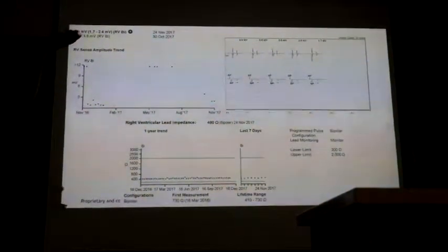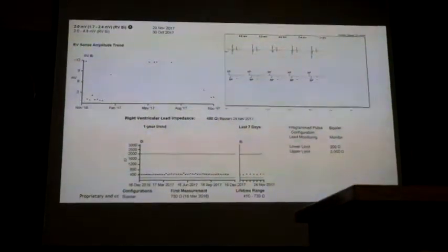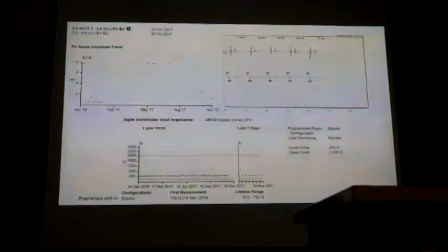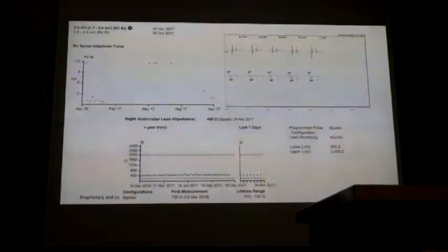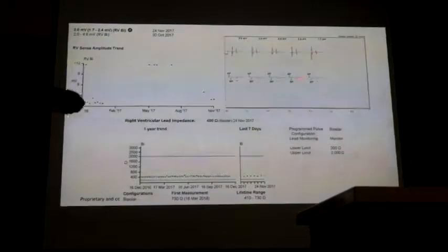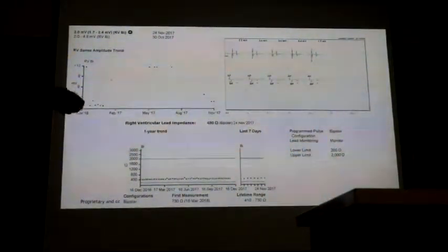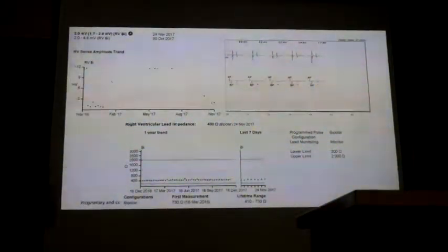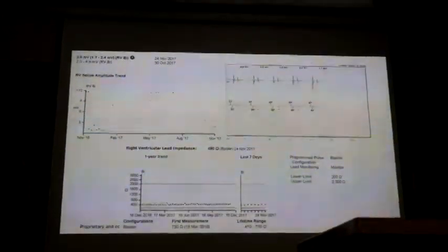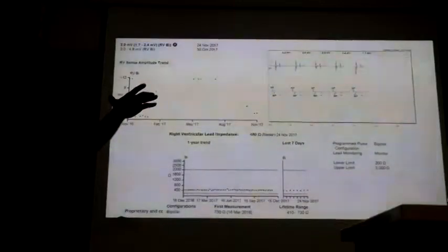You're going to pace and take the measurement when you pace, so it won't make any difference. You could do some weird stuff, like program it to trigger pace, and you might be lucky and pick it up. But just because the impedance is stable doesn't mean the lead's okay. That's the point - we've got extra signals going on that are not physiological, and it fits with a fractured lead.